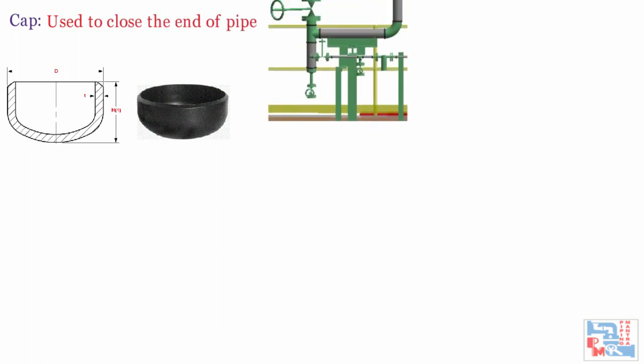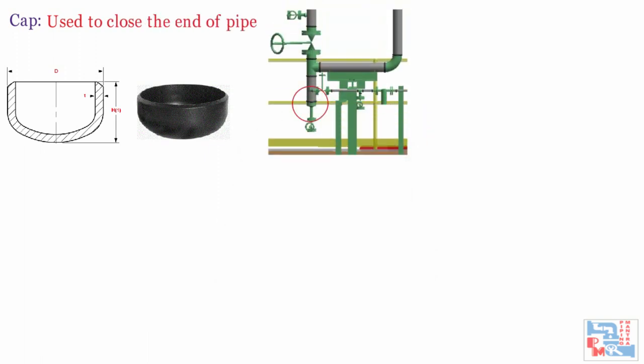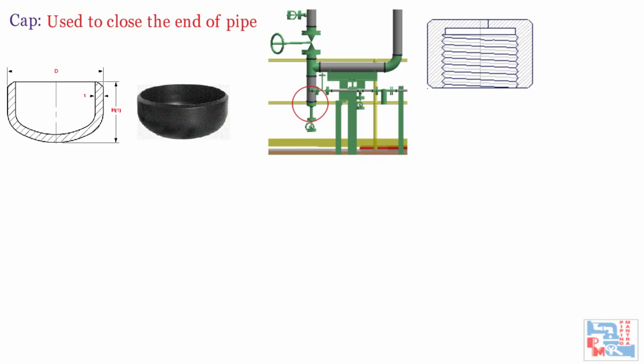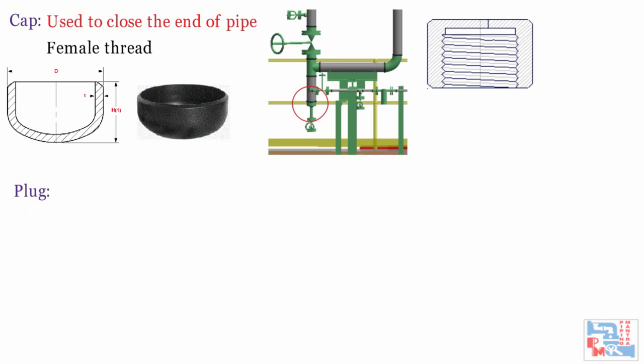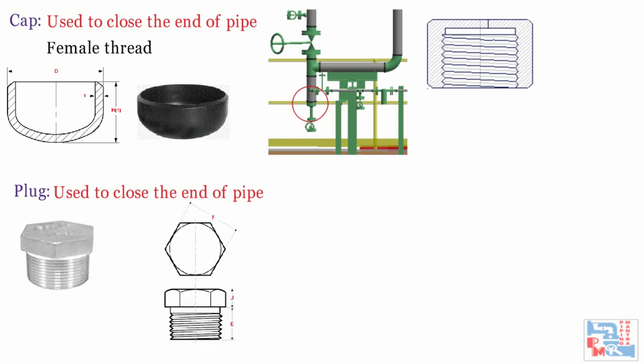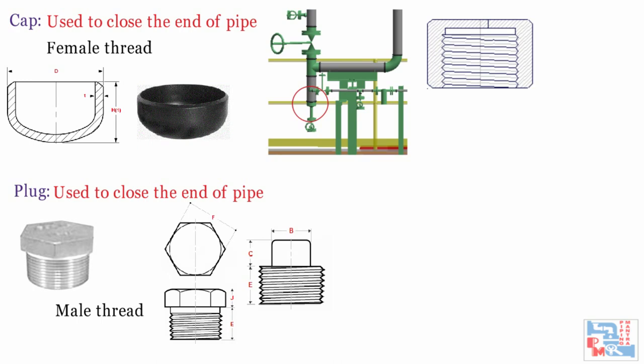Next is the cap, used to close the end of a pipe by butt weld, socket weld, or threaded connection. The cap has a female thread. The plug is another end closure used to close the open end of a pipe component like a half coupling or valve by threaded connection below 2 inches. Plugs have square, hexagonal, and circular heads. In function, a plug is similar to a cap, but a plug has a male threaded end while a cap has a female threaded end.